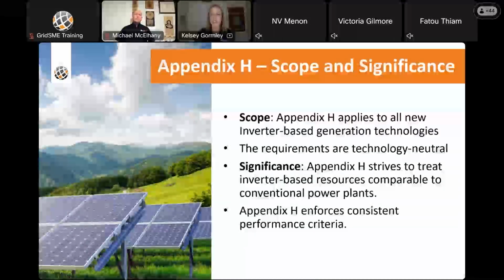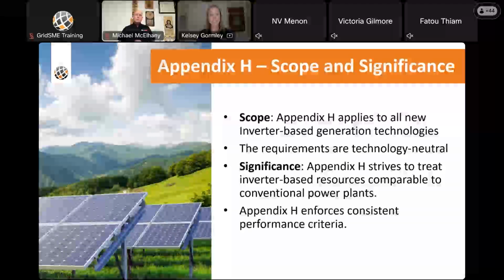All right, so again, not to reiterate myself too much here, but Appendix H was created to ensure that all new inverter-based generators meet additional performance and data sharing standards beyond just the basic interconnection requirements. CAISO introduced this appendix specifically to tackle the unique attributes and behaviors of inverter-based resources such as PV and batteries, and to prevent those issues from causing large-scale grid disturbances. The focus is on making sure that these resources can ride through grid disturbances, provide voltage support, and not adversely affect stability from day one. Appendix H fills that gap by spelling out exactly what an IBR plant must be capable of before it can interconnect.